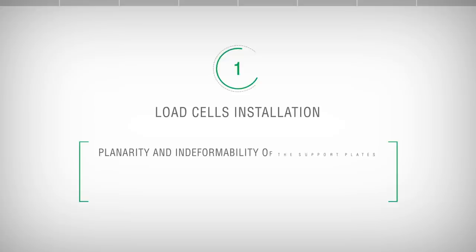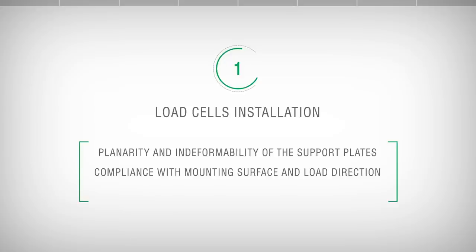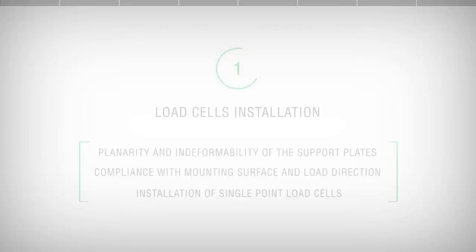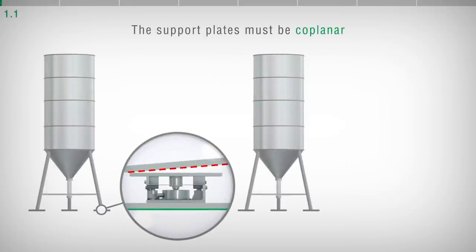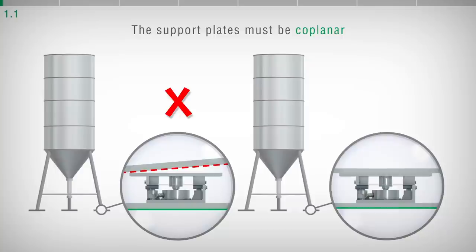Load cells installation: planarity and indeformability of the support plates. Compliance with mounting surface and load direction. Installation of single-point load cells. Check that the load cell's support plates are coplanar and, as a rule, planar.